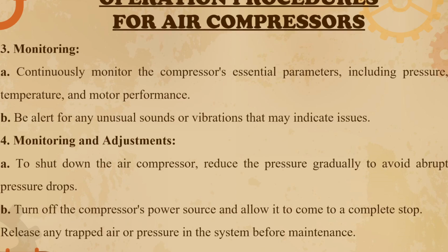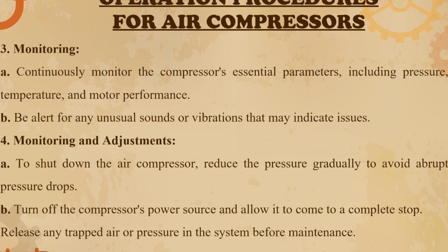Third is monitoring. Continuously monitor the compressor's essential parameters like pressure, temperature, and motor performance. Also, be alert for any unusual sounds or vibrations that may indicate issues. Fourth is the shutdown. To shut down the air compressor, reduce the pressure gradually to avoid abrupt pressure drops. Turn off the compressor's power source and allow it to come to a complete stop. Release any trapped air pressure in the system before maintenance. Fourth procedure rather is shutdown procedure. Sorry for the typographical error.